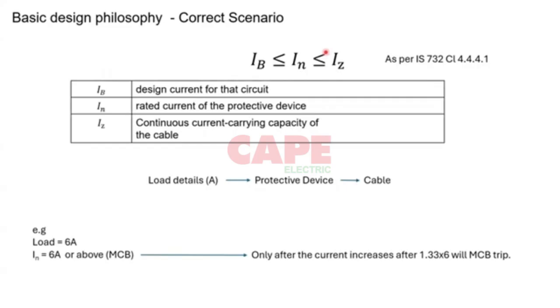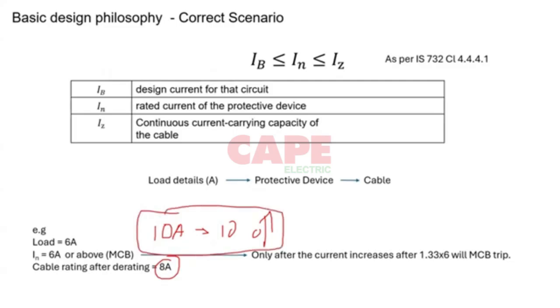Generally, it is better to go above. Suppose you go with something around 10 amps for the MCB. Then the cable size should be for the 10 amps MCB. So if you're going with a 10 amps MCB, due to the client or anything like that, then the cable should be rated for 10 amps or above. This is the basic expression, which is very important. After that, you look into the voltage drop and all those other things. With this, you will not be oversizing the protective devices, you will be sizing them correctly, and you will also have an approximately good size of cable.